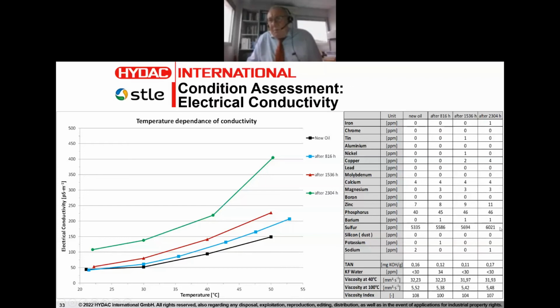Sulfur content has remained the same. It's a thiophosphate additized fluid, but obviously with some native sulfur present as well, because the ratio would not be 10 to 1 or 100 to 1, in fact. It would be somewhere more like 2 to 1. One of the most encouraging things is that water has not changed. Yeah? So we're dealing with the same water content. So we cannot ascribe these changes in conductivity to changes in the water content. And the acid number has remained the same.